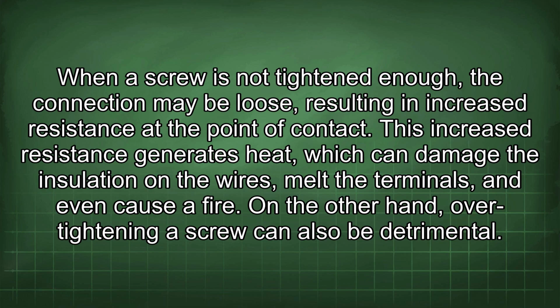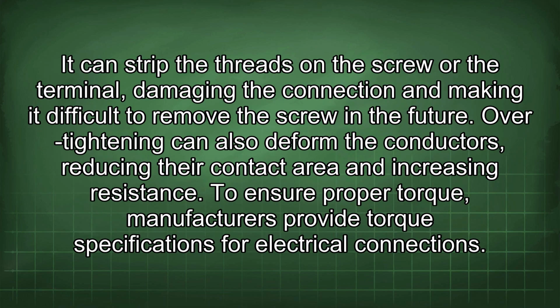a fire. On the other hand, over-tightening a screw can also be detrimental. It can strip the threads on the screw or the terminal, damaging the connection and making it difficult to remove the screw in the future. Over-tightening can also deform the conductors, reducing their contact area and increasing resistance. To ensure proper torque, manufacturers provide torque specifications for electrical connections.